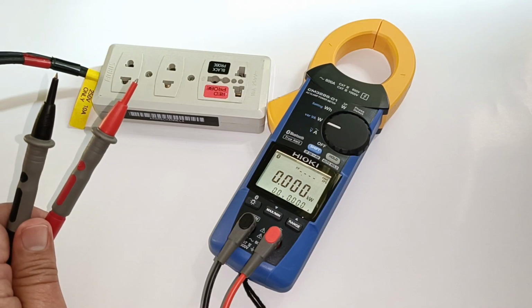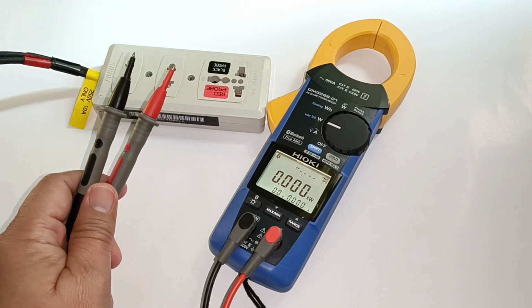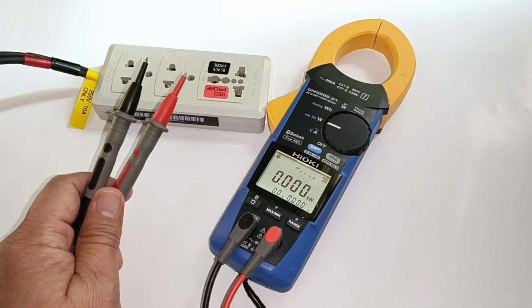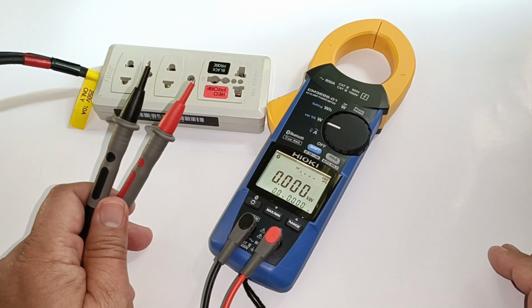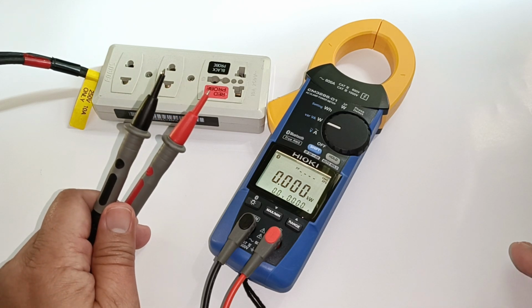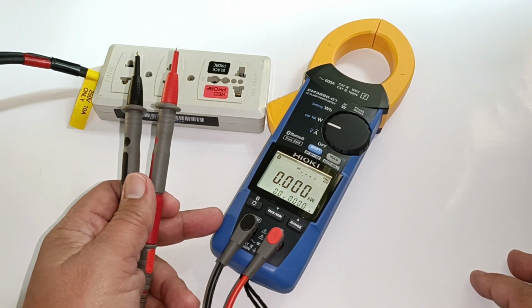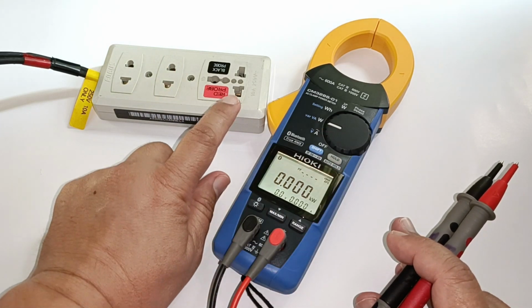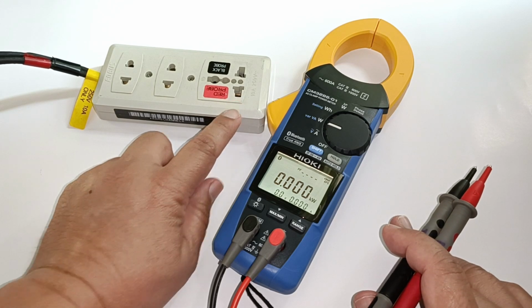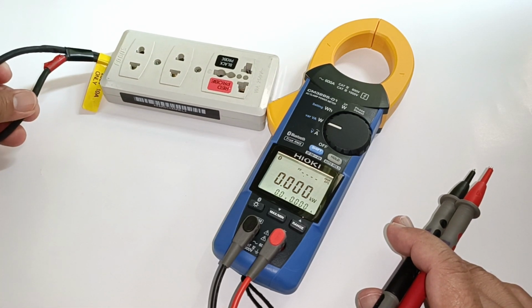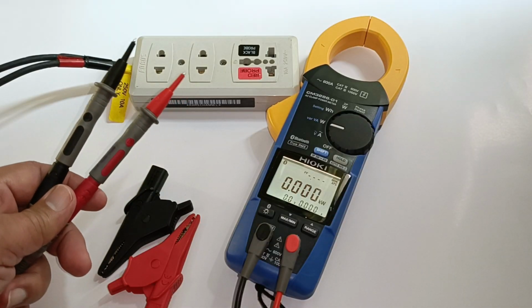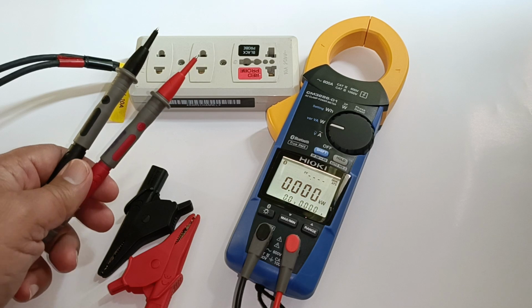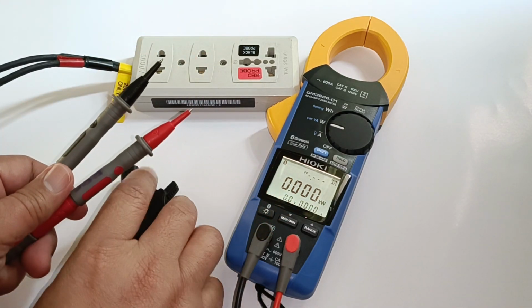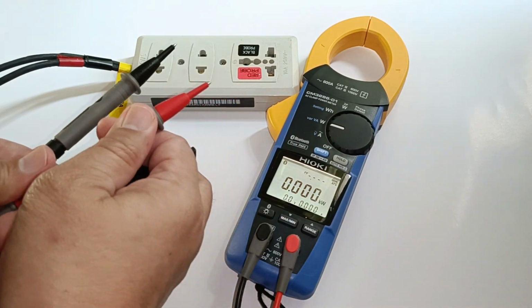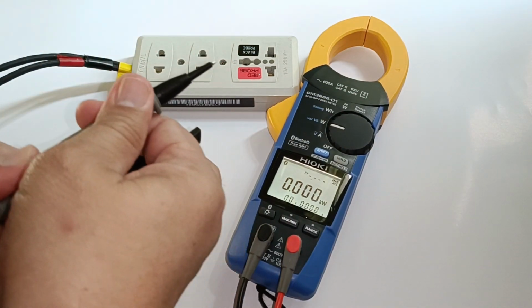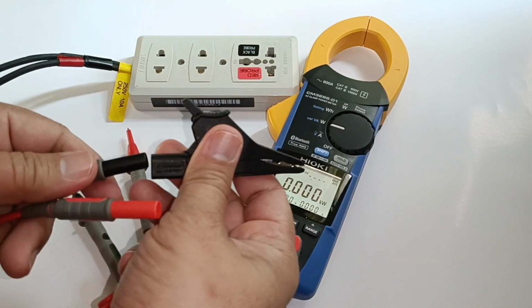To measure power, you need access to the voltage supply for the voltage probes and access also to the conductor or cable for the current sensor to clamp on simultaneously. Let's take a simple single-phase load to demonstrate the power monitoring of the Hioki CM3286-01. The load will be connected here for its voltage source, and the current sensor will be clamped on one of these cables. Take note that this is just a simple simulation. In practical situations, this outlet here could actually be a panel board or a big circuit breaker, and instead of using the needle tip voltage probes, you could actually use instead alligator clips.